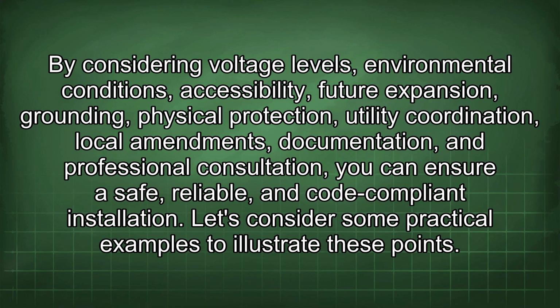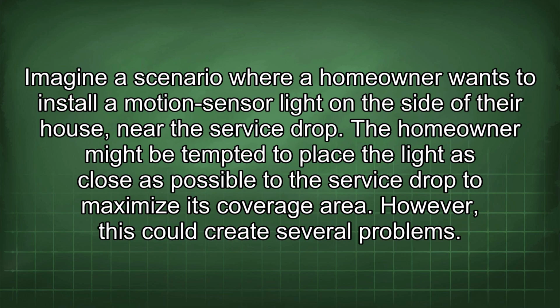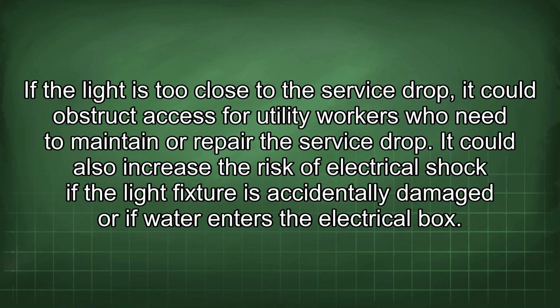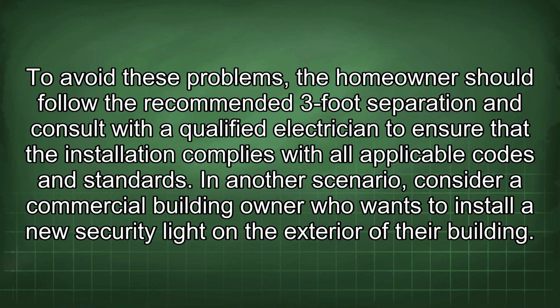Let's consider some practical examples to illustrate these points. Imagine a scenario where a homeowner wants to install a motion sensor light on the side of their house, near the service drop. The homeowner might be tempted to place the light as close as possible to the service drop to maximize its coverage area. However, this could create several problems. If the light is too close to the service drop, it could obstruct access for utility workers who need to maintain or repair the service drop. It could also increase the risk of electrical shock if the light fixture is accidentally damaged or if water enters the electrical box. To avoid these problems, the homeowner should follow the recommended 3-foot separation and consult with a qualified electrician to ensure that the installation complies with all applicable codes and standards.